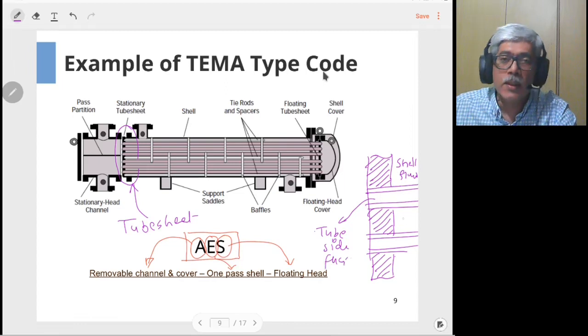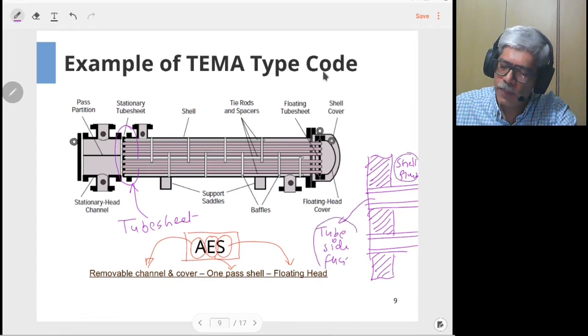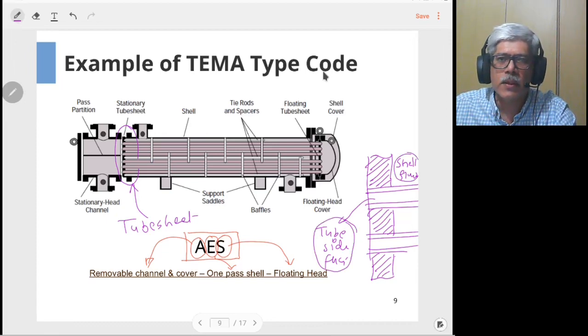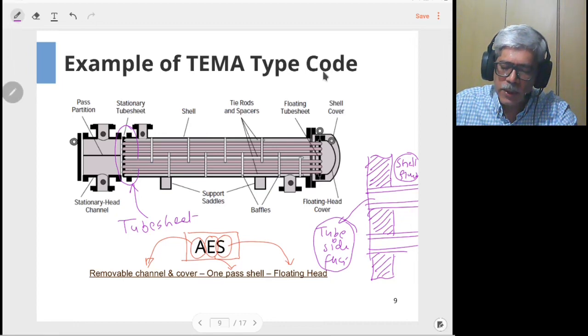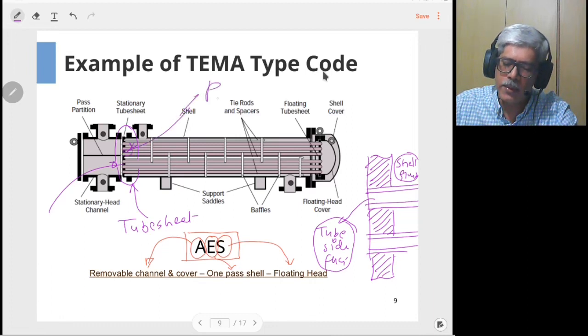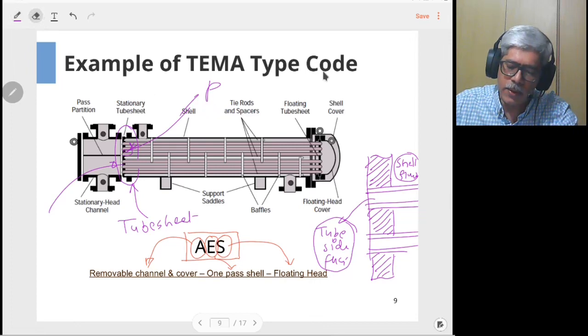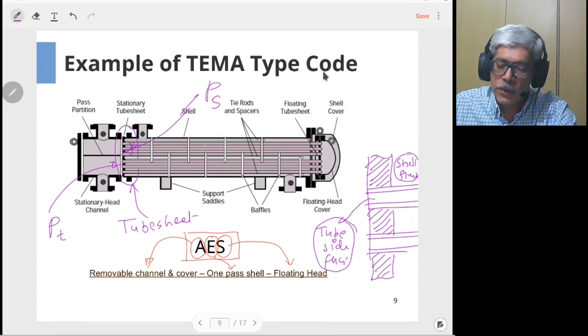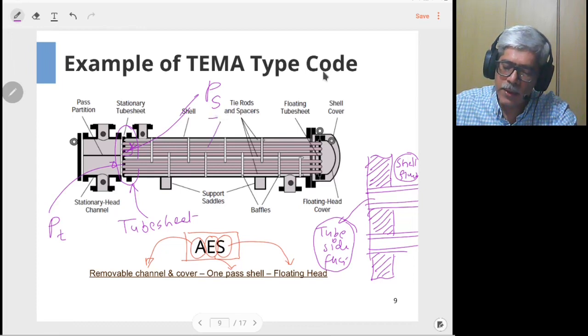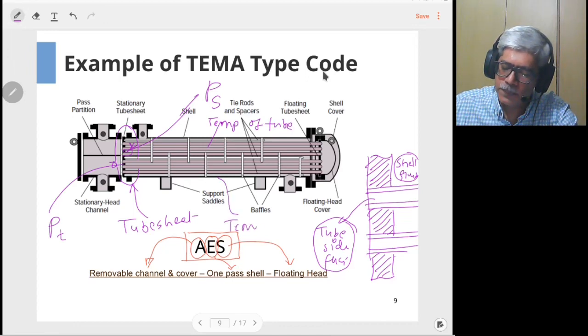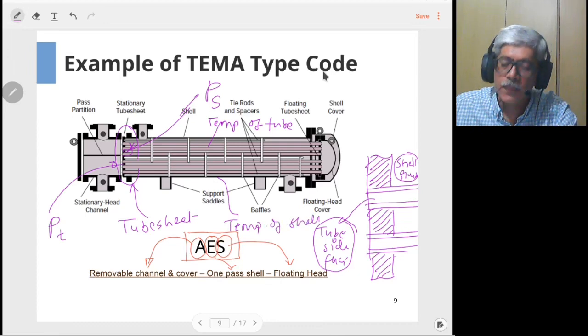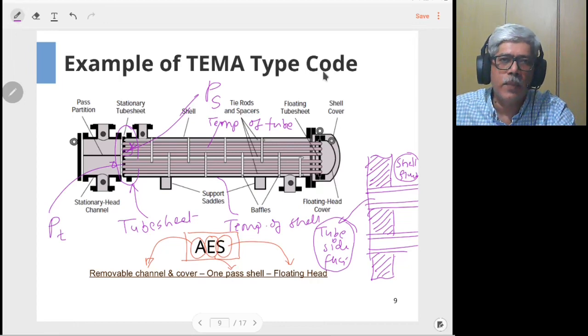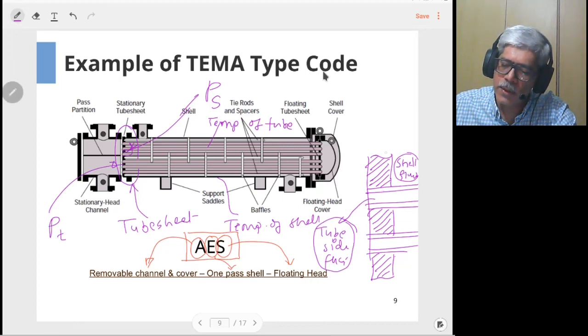This component is subjected to mechanical loads: pressure from the shell side fluid and pressure from the tube side fluid, which act on either side of the tube sheet. In addition to that, the tubes will have a different temperature than the shell. As a result, there is a differential expansion between the shell and tubes, which is an additional load on the tube sheet.